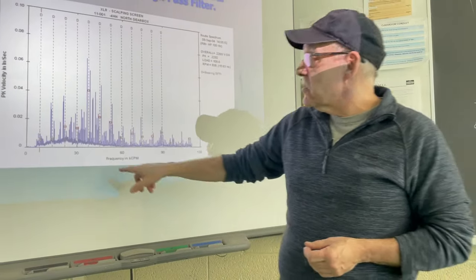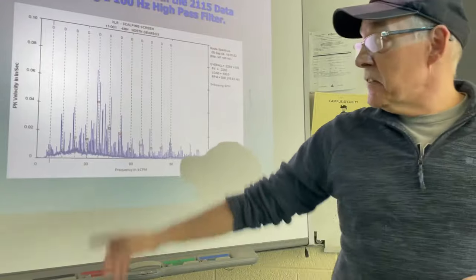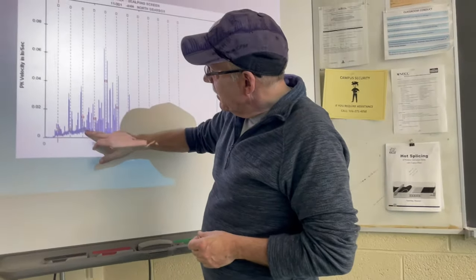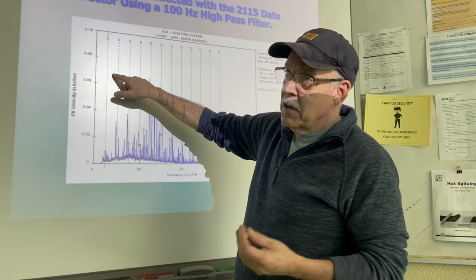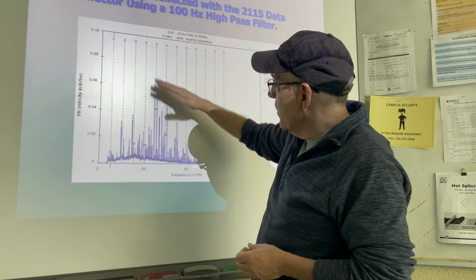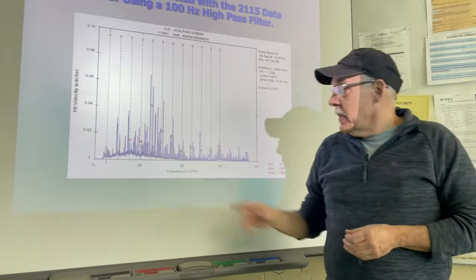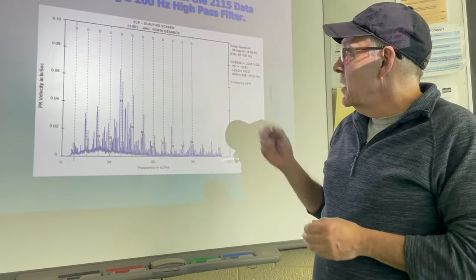Right about now, this is like, change me now, right? Because if I let this go any longer, what's going to happen is all this is going to go away. And then this raised floor noise is going to, so I'm going to get one thing at one times, because the thing's loose or whatever. And then I'm going to get all this raised floor noise, and all these other peaks are going to go away on me. So that's just experience when you look at things so many times.